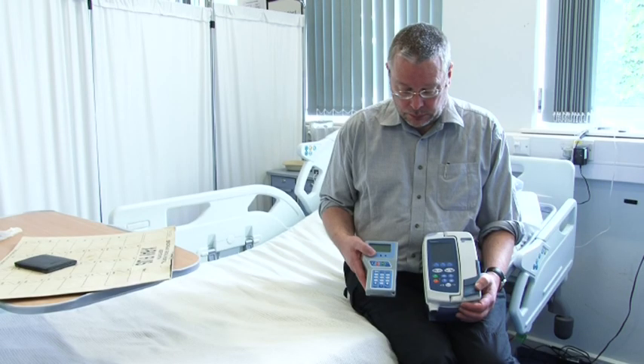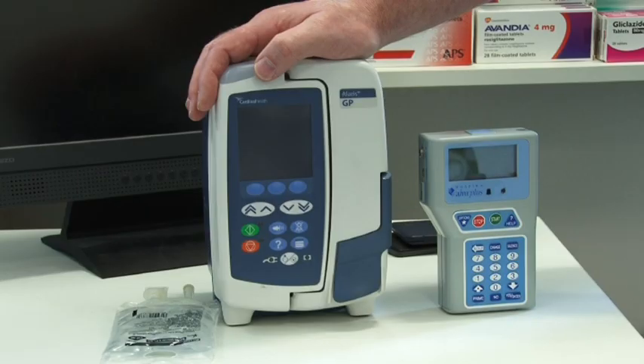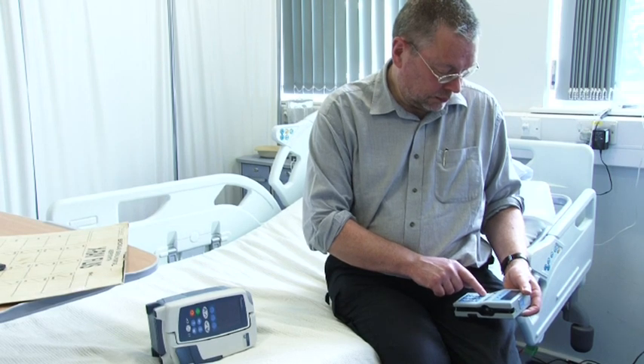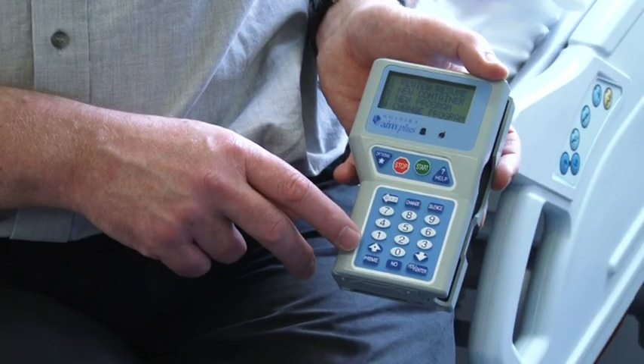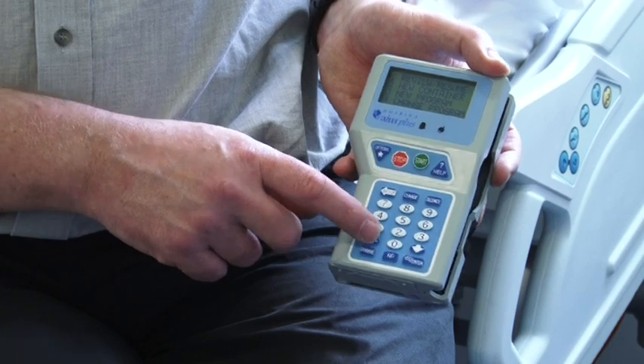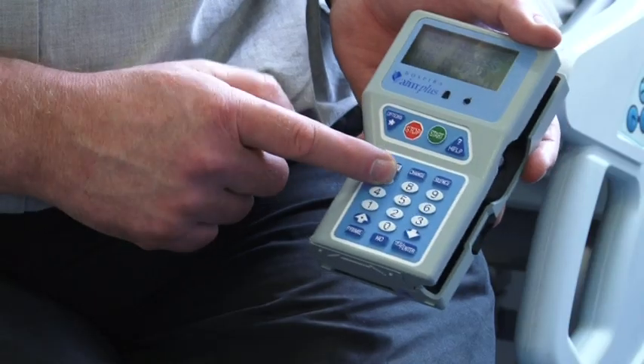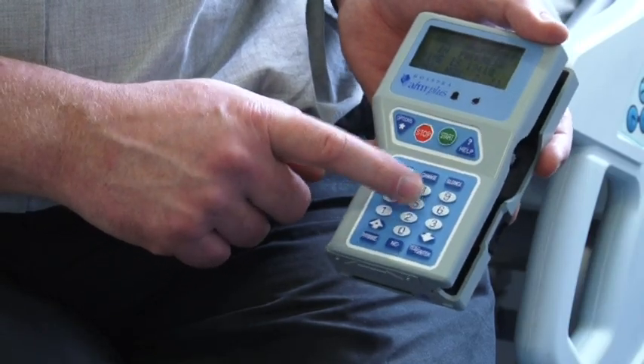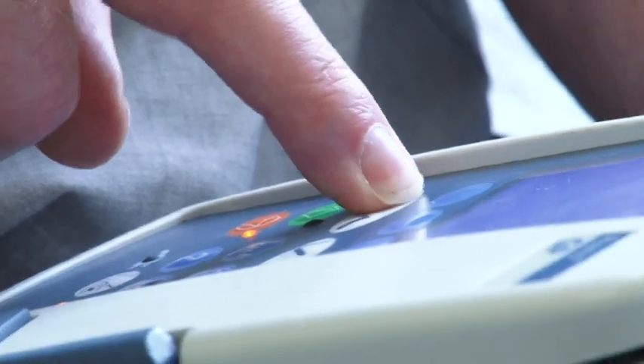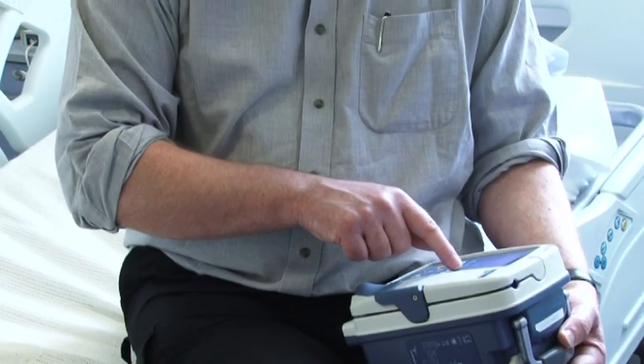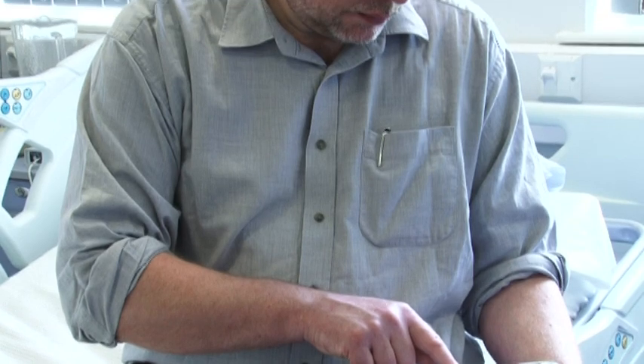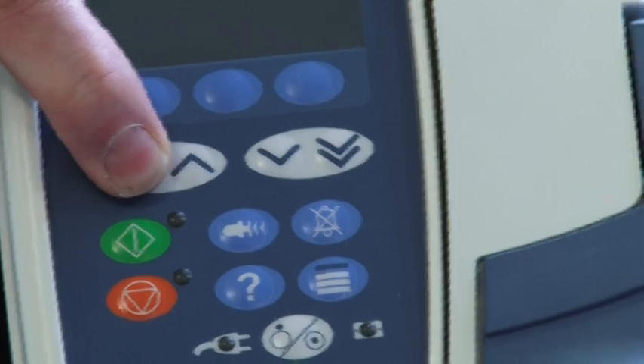I'm arguing that design can make things safer. There are two sorts of infusion pump, and the question is, which design is better? One has a calculator keypad, so if you want to enter a number like 12.3, you key in the digits 1, 2, 3. The other is an incremental keypad, where if you want 12.3, you press up and down, gradually increasing the number through 10, 12, 12.3, or decreasing it from 100 down through 90, 80, 70 to 12.3.